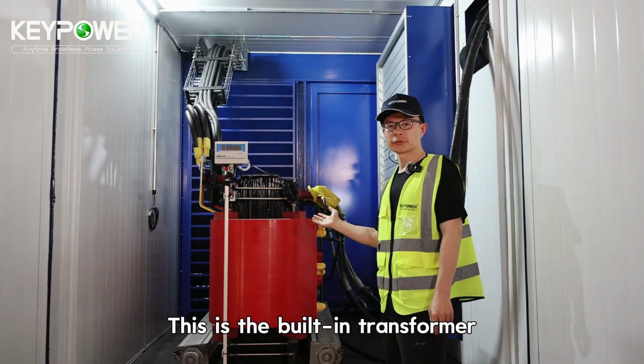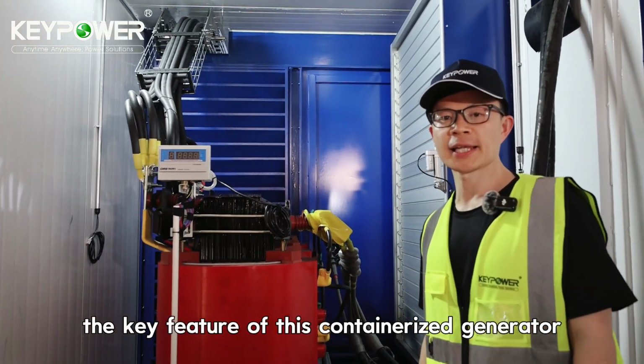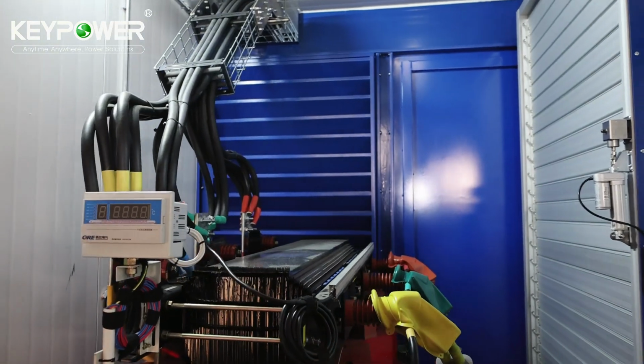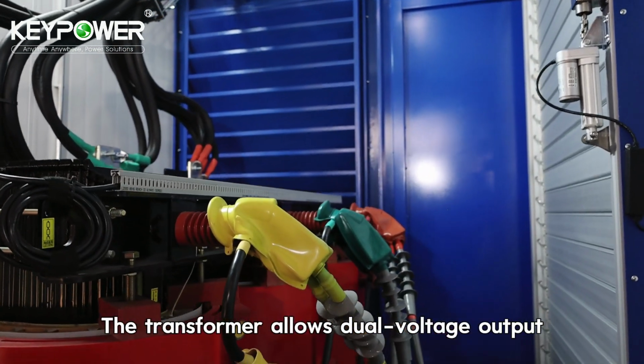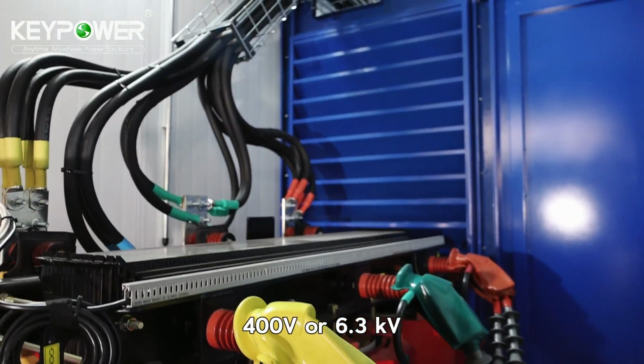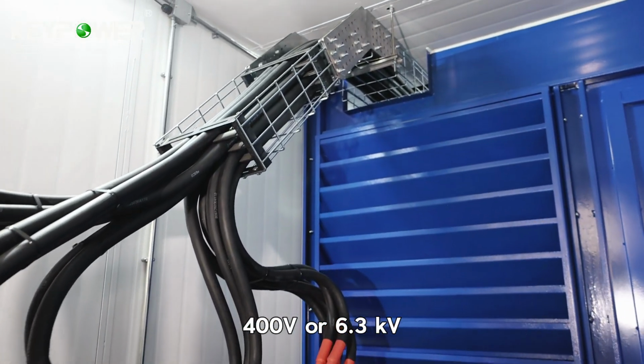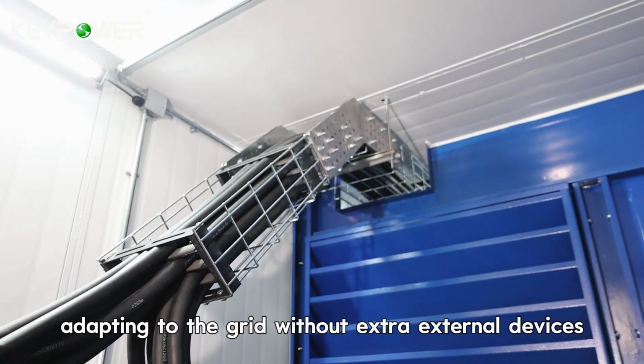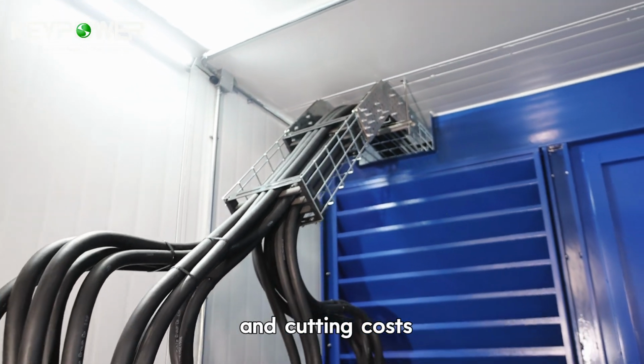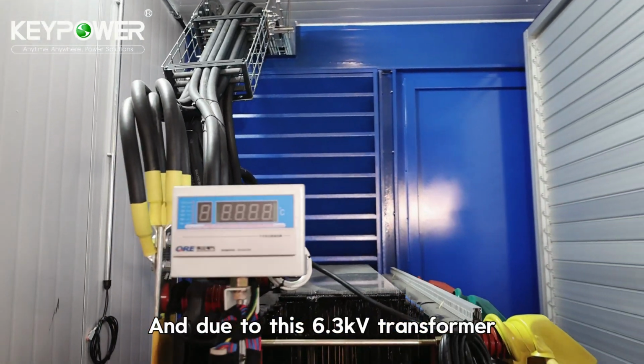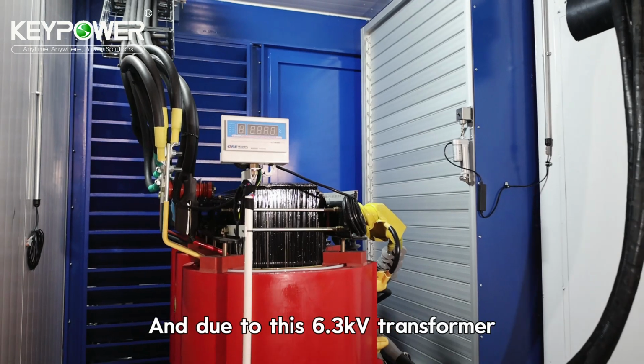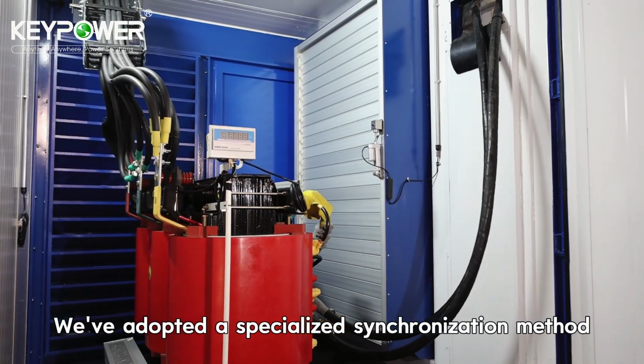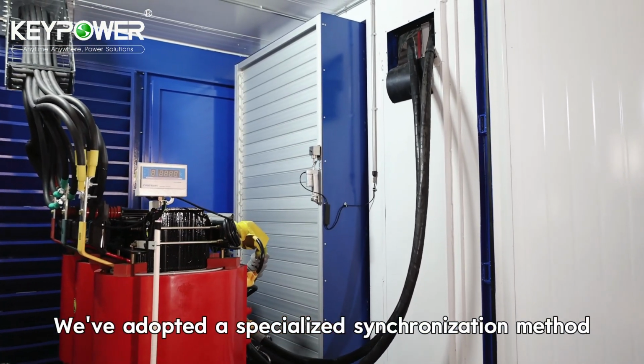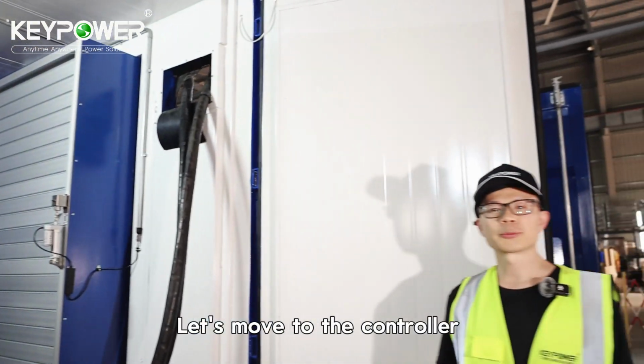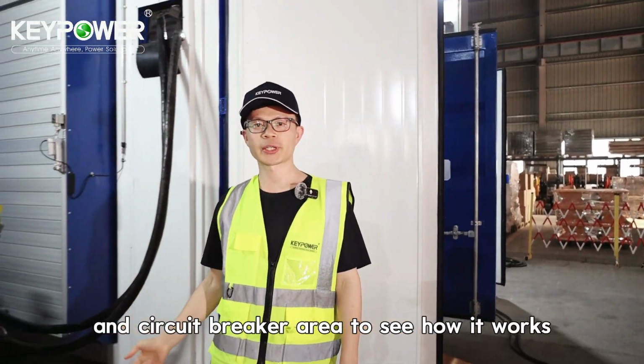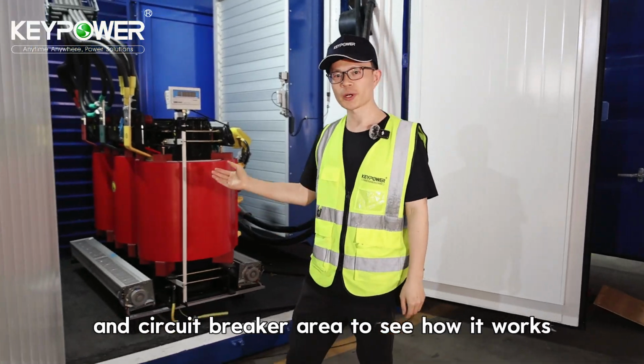This is the built-in transformer, the key feature of this containerized generator we made this time. The transformer allows dual voltage output, 400 volts or 6.3 kV, adapting to the grid without extra external devices and cutting costs. And due to this 6.3 kV transformer, we've adopted a specialized synchronization method. Let's move to the controller and circuit breaker area to see how it works.